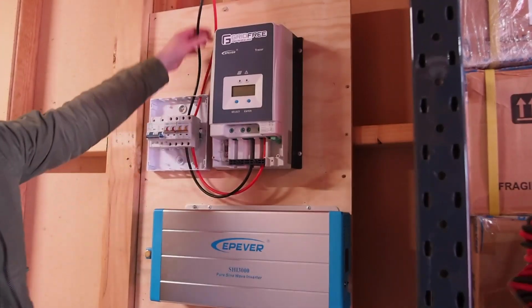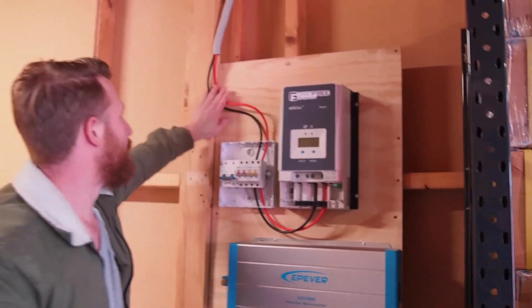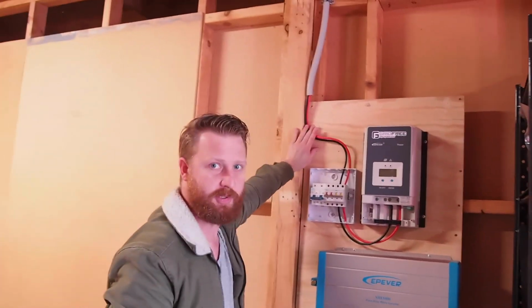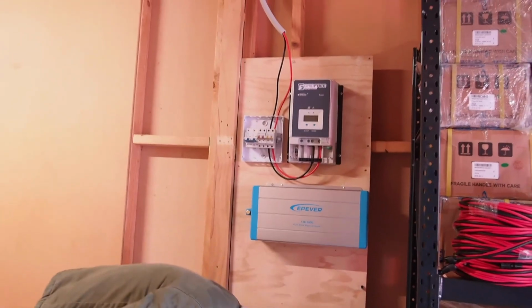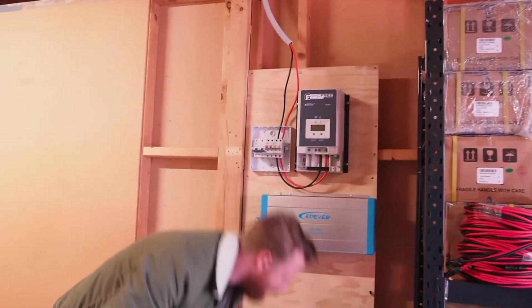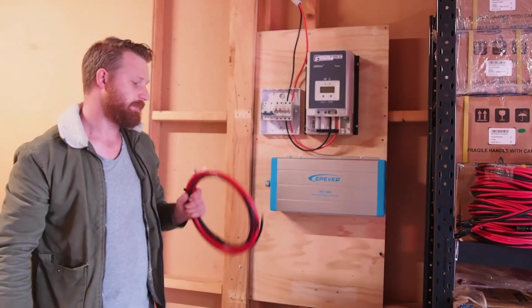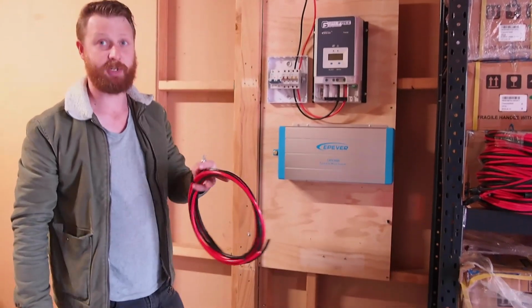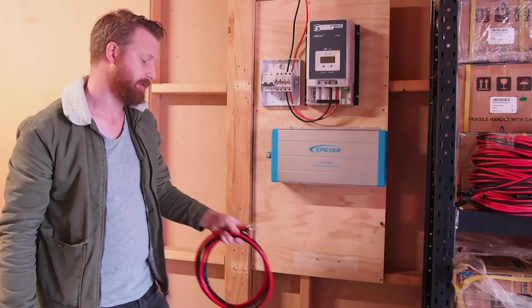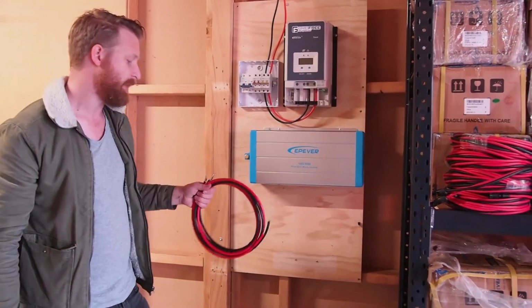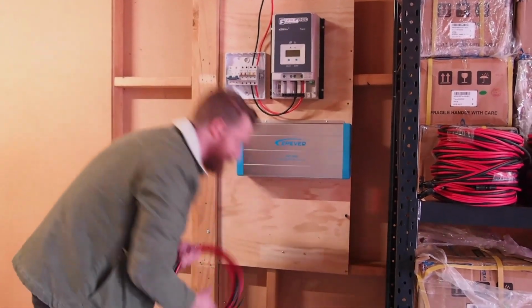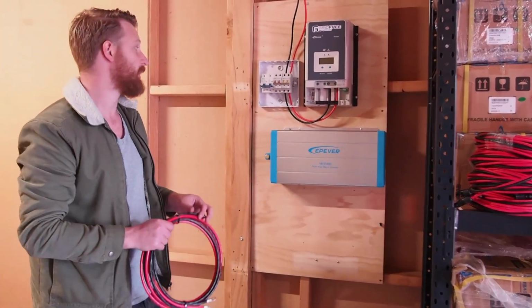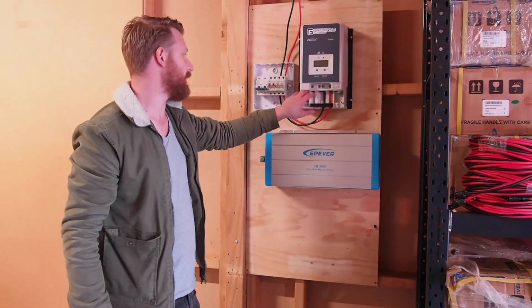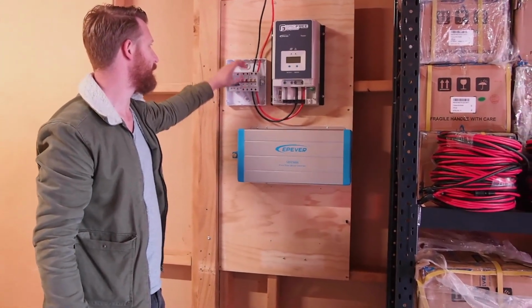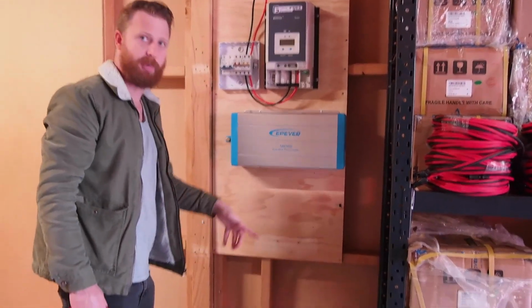So now we've got the solar cable run, we're going to start on the cable that runs through to the battery. Now included in our kits is 16mm cable, which comes pre-crimped with terminals that screw straight onto the battery terminals. And we use the 16mm, the thinner cable of the two, to run from the charge controller into the circuit breaker, from the circuit breaker down to our battery bank.